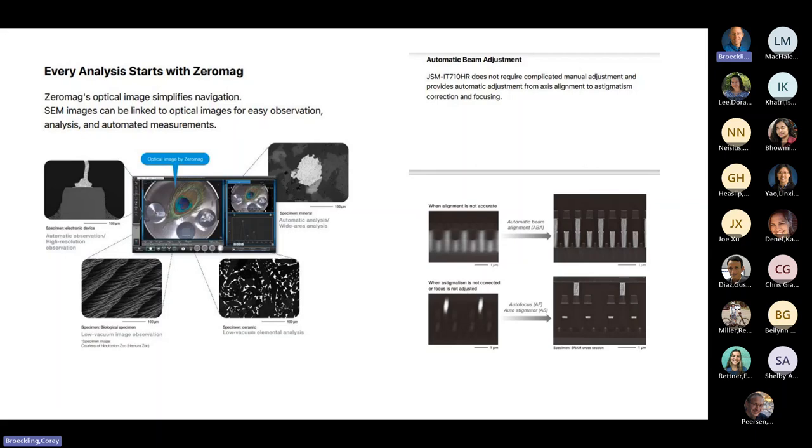What's going to be interesting to the casual user, you push a button and it automatically focuses the thing. Then you have the other thing is astigmatism. When you see shape deformation in one direction, you push the automatic astigmatism button and it stigmates it for you. This works at low mag, so your learning curve is substantially short for how to do good imaging.